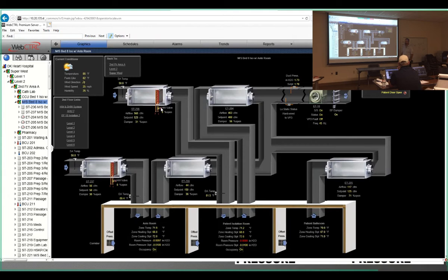It's a dedicated exhaust fan for this isolation room as well, which is worth mentioning. Each of the isolation rooms has its own exhaust fan, so you're not trying to share it. Probably just in my experience, when you've got an isolation room problem, a lot of times it's going to be the exhaust. If you're not getting enough negative static, then it's going to be your exhaust fan. That's the only piece that's in the exhaust system in those.